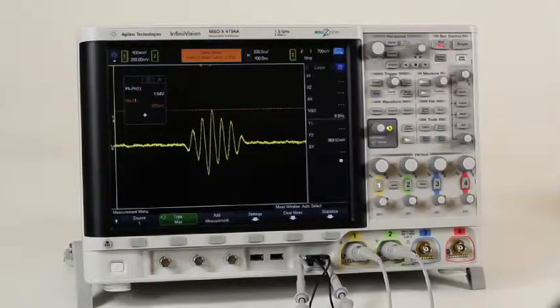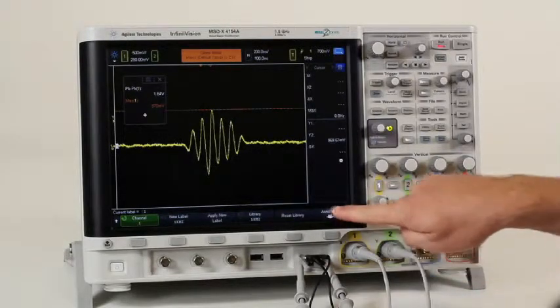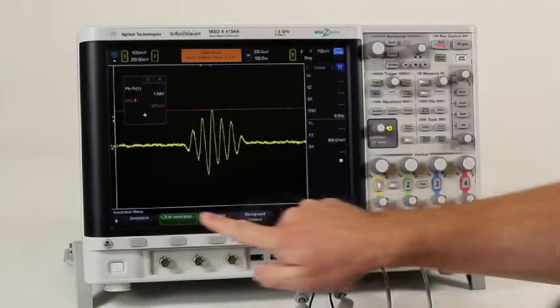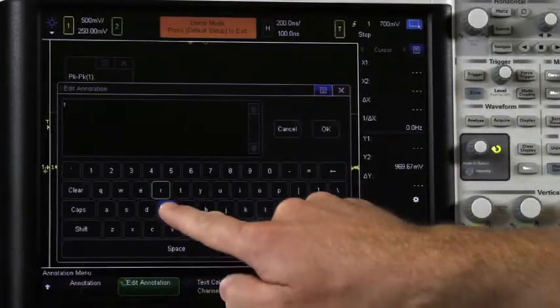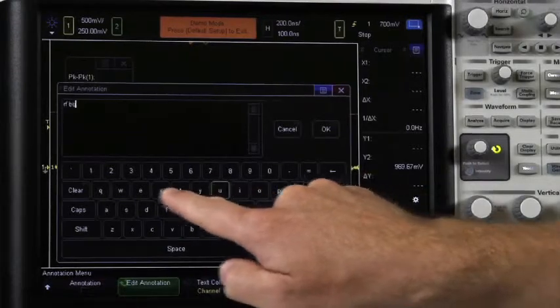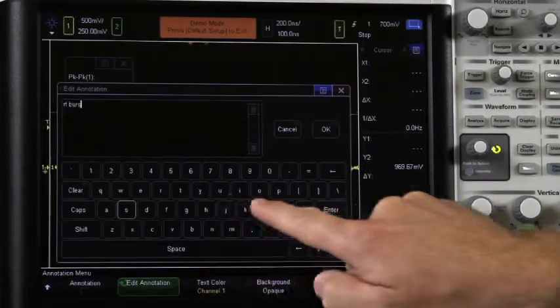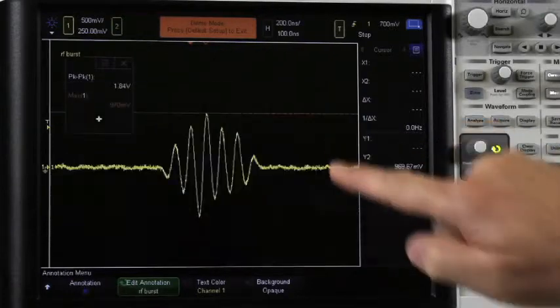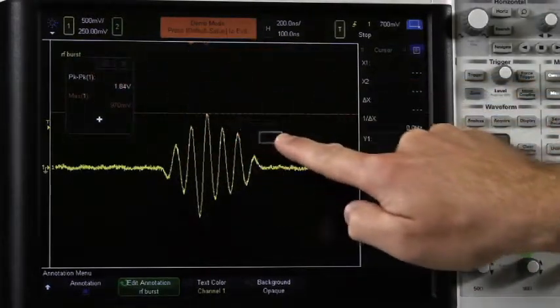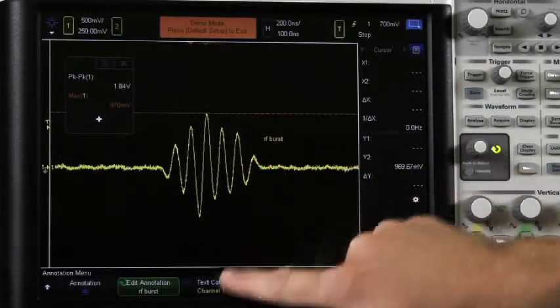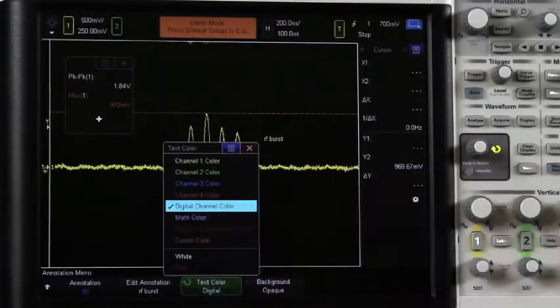From a documentation standpoint, as a customer, I can easily add on-screen annotations. I'll simply press the label front panel button, then annotation soft key, and select edit annotation. A nice design for touch keyboard pops up. I'll type in a brief message to remind me of what the signal was, and I can now move this annotation box around screen, change its color, and change its background color.